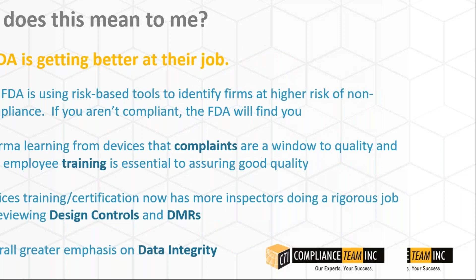So what should your action plan be now that you know what these compliance actions are? Well, the first one is you should do a self audit. One of the findings in the top 10 for devices was quality auditing. So this should be just something that you do anyway, especially if you're a device manufacturer. But do a self audit, and you want to dig deep on those complaints and data integrity and quality unit and all those things that are in the top 10. Especially with the things in the top 10 that you really feel, based on our poll, you might be weak on.